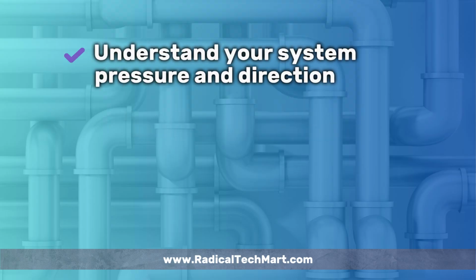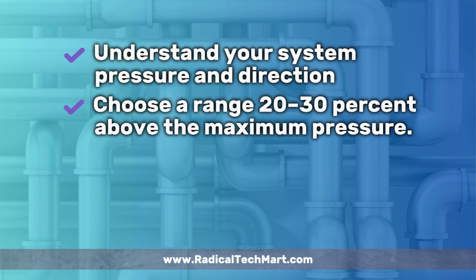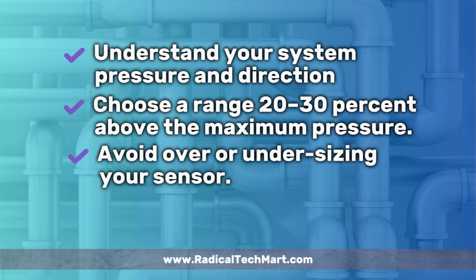To summarize, understand your system pressure and direction, vacuum or positive. Choose a range 20 to 30% above the maximum pressure. Avoid over or undersizing your sensor.